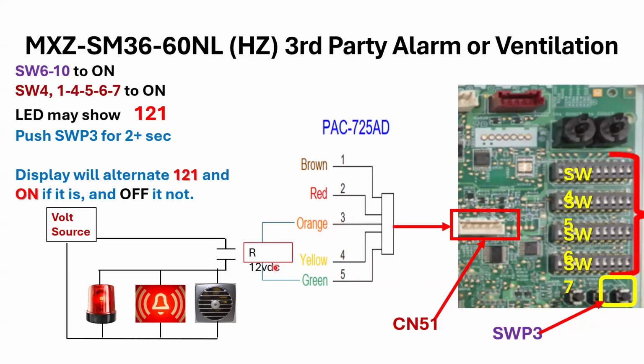And then you would put our CN24 relay kit. That's a Mitsubishi relay kit, a 12-volt DC relay that gives us a dry set of contacts. So it would close these contacts, and then that would trigger whatever type of alarm you wanted to do. And this is just an output from the outdoor unit to trigger an alarm to let someone know there's a refrigerant leak, or there's an alarm for that setup. So again, it's telling you through the dip switches on the outdoor unit, this is how you set it to on. LED may show 121, and then you push our SWP3 button. That's how you make the setting take effect.